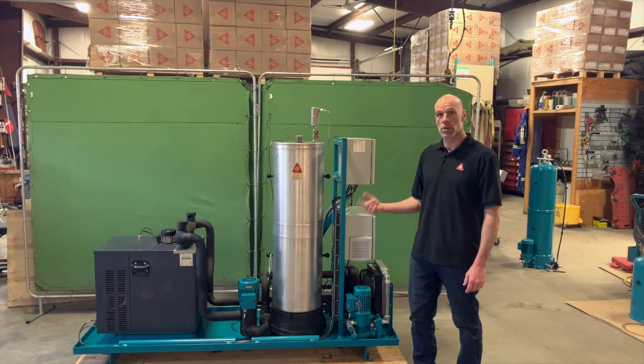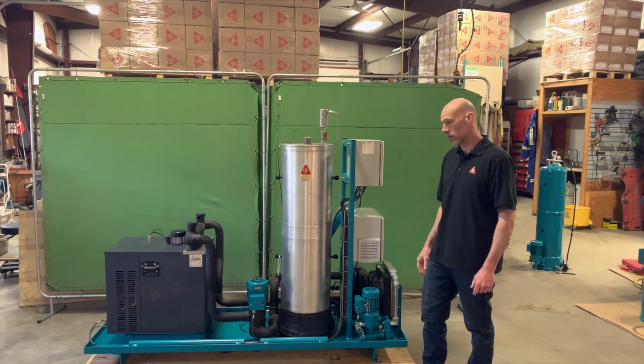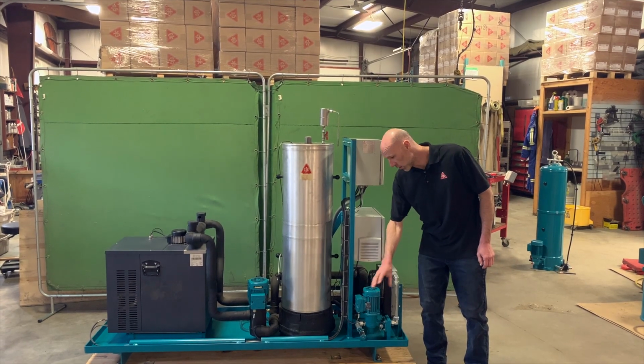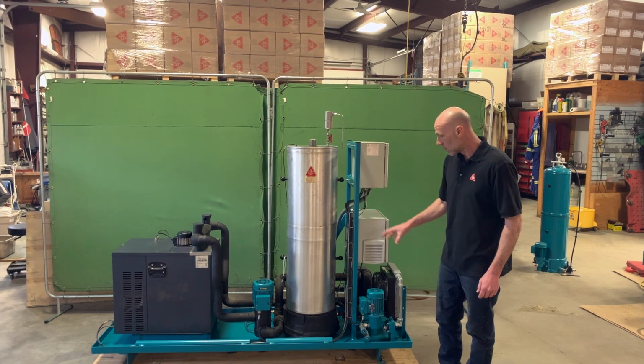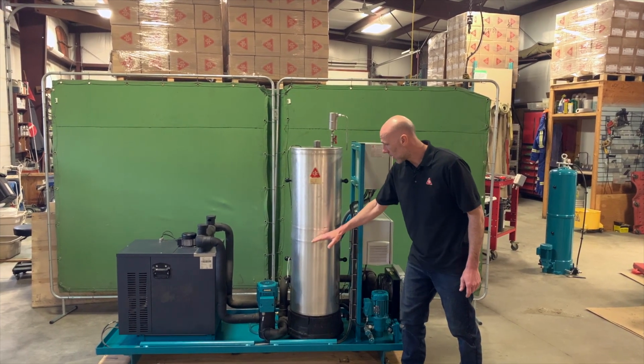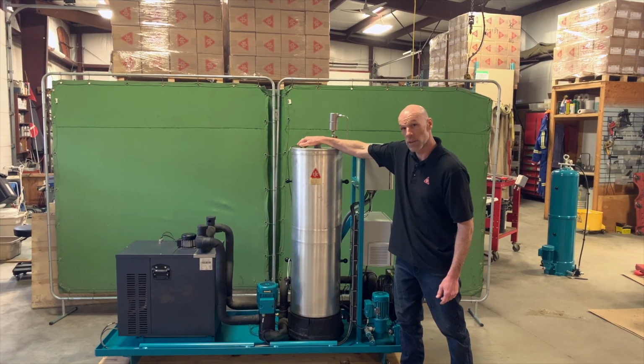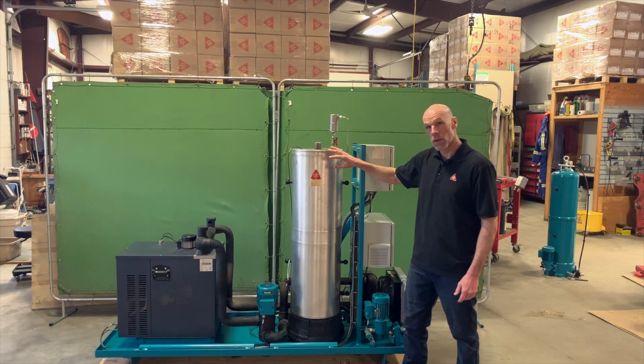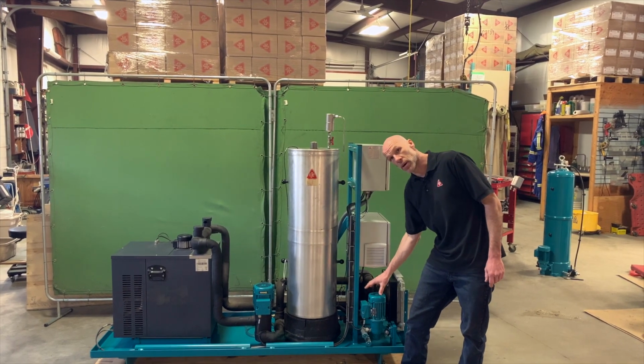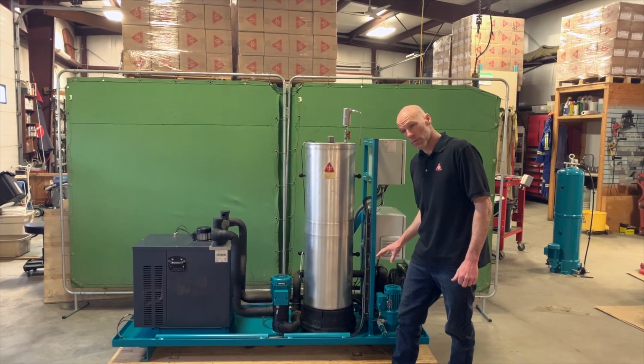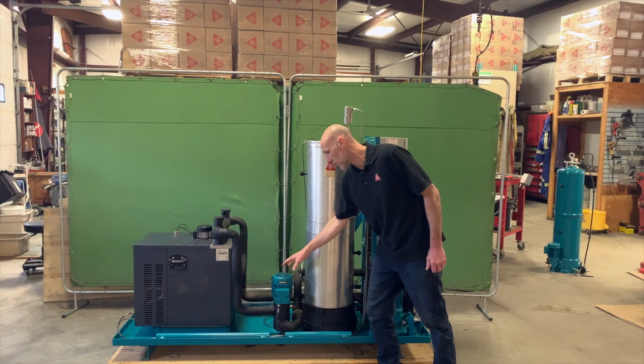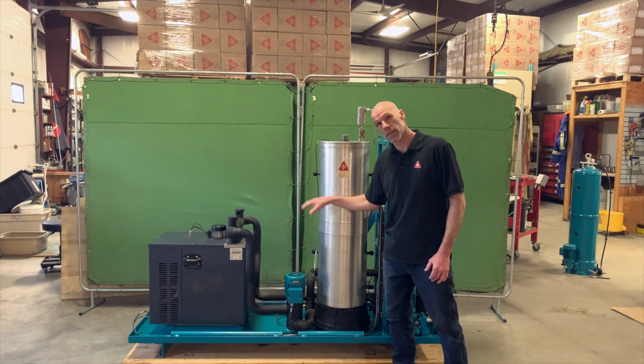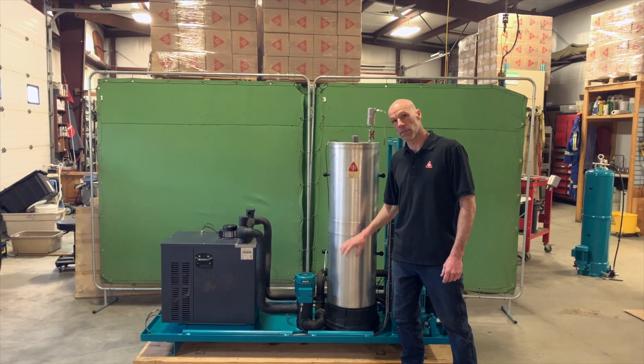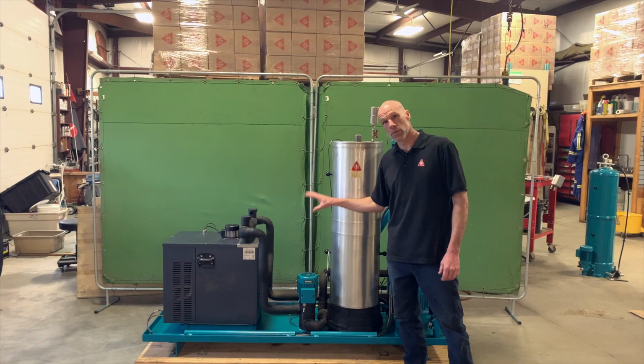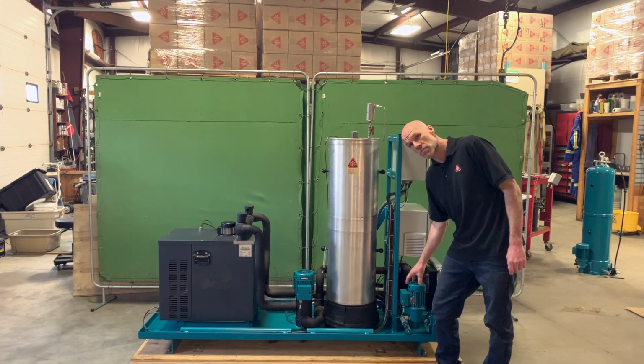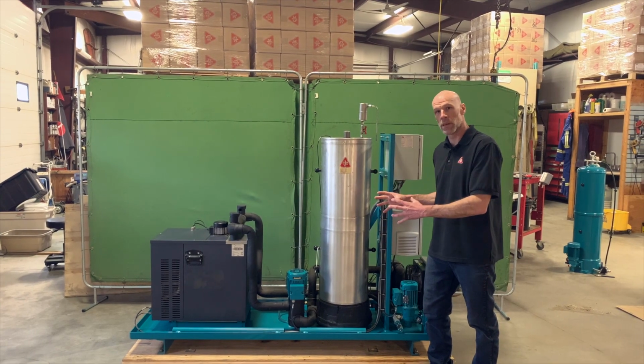So when you start the unit, it's going to go through an automated sequence to make sure that everything is happening in the right order. The first thing that will happen is the inlet pump will run. This is drawing oil from your system into the VRU. From here, it's going to start by filling the filter housing, and as it comes up to the proper level, there's a level sensor in the housing so that it knows that it's full of oil. Once that happens and the housing is full of oil, you'll see the inlet pump turn off. So once the inlet pump stops running and the filter housing is full, the circulating pump will turn on, and it's going to start moving oil through the filters and through the chiller. That's going to bring the temperature of the oil down to help the varnish precipitate and to be captured by the filters. Once it's down to a proper temperature, then the inlet pump will start running again simultaneously with the circulating pump, and the system will begin normal operation.